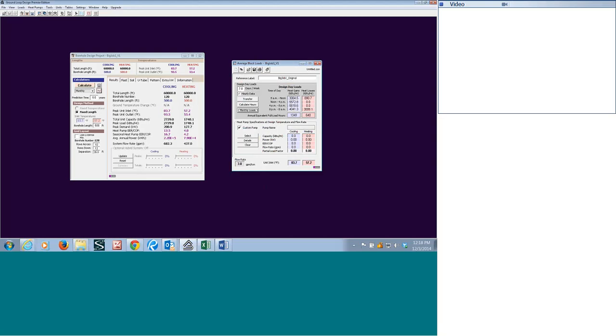So if we've got this new load file, we also have to go back and make sure we've got the right heat pump selected. Because what the heat pump library file is going to do, it's going to allow the software to calculate the efficiencies at different entering water temperatures. This is another issue we find with some forensics, where someone will use a central plant or a heat pump that doesn't have good data, so they'll use another heat pump's performance profile, and you get a lot of errors if that equipment is not equivalent to the one you've selected. So just keep that in mind as well. So we've got the new file. What we're going to do is delink. I always do this, and then relink the load data and zone data back to our loop simulation. Now we're going to hit run again.